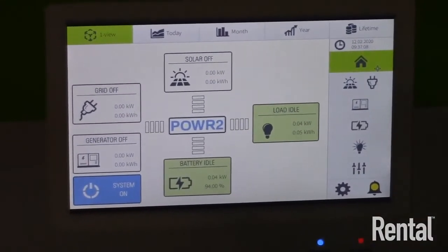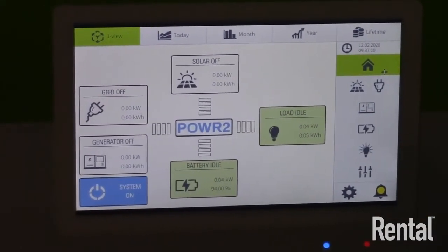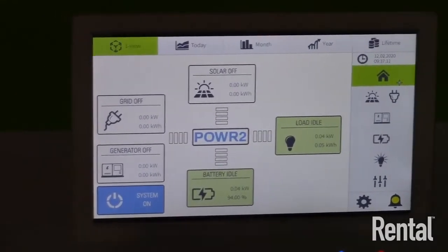Now this system will automatically sense the load and tell the generator when it's needed and when it can be shut off. So at periods of low load, we run primarily from the battery, and then we only restart the generator based on two parameters. Number one, if the battery reaches 10%, we call the generator to switch on and recharge the battery. Number two, if the load spikes up above what the hybrid is able for, we call for the generator and seamlessly switch over to generator power.